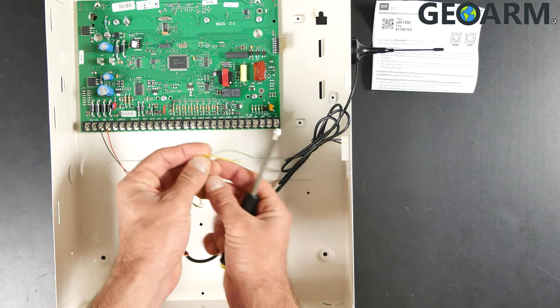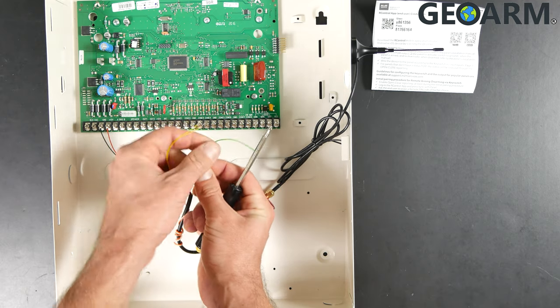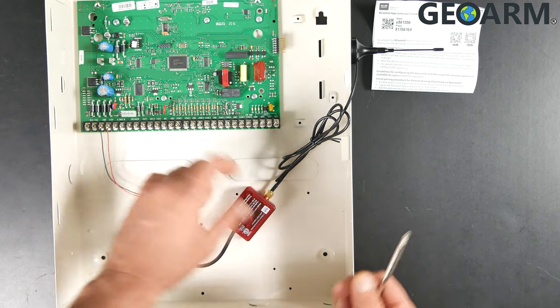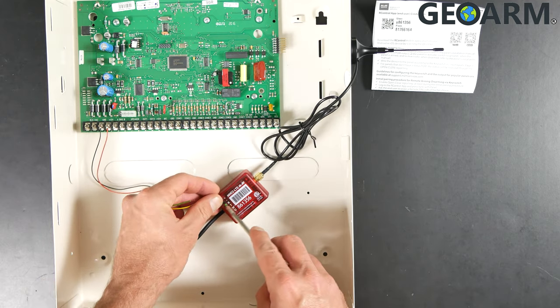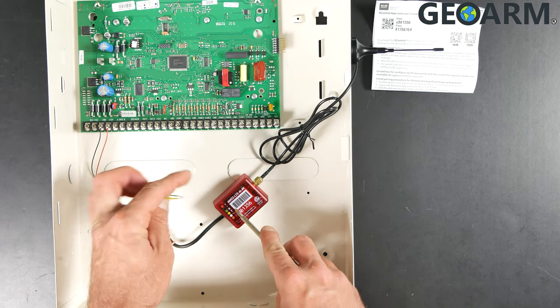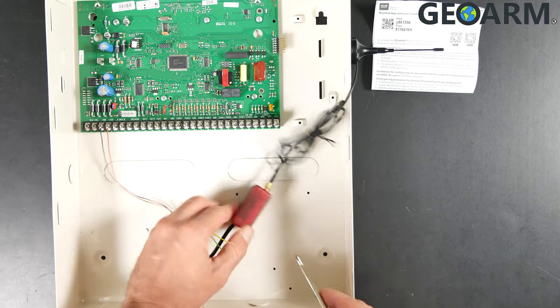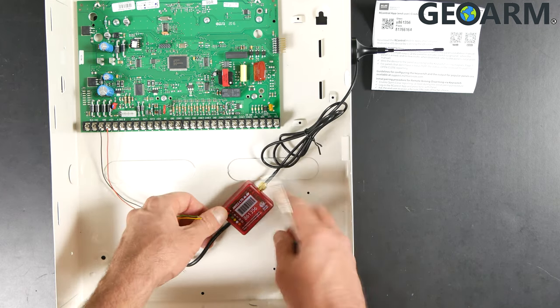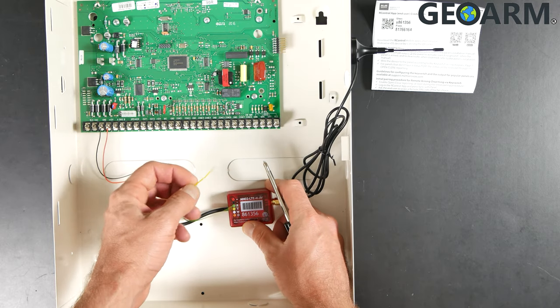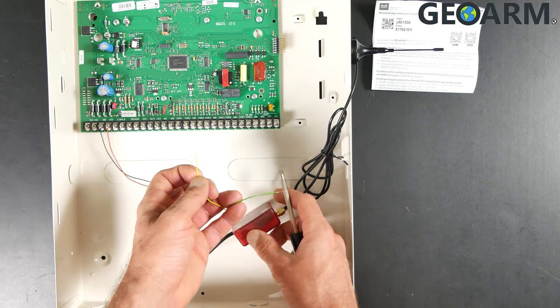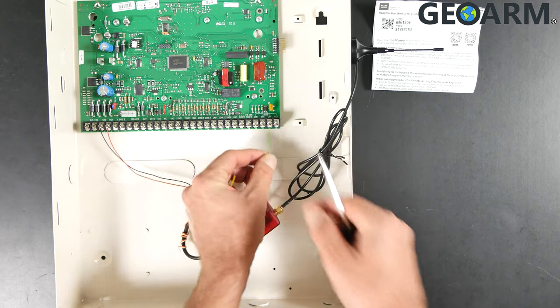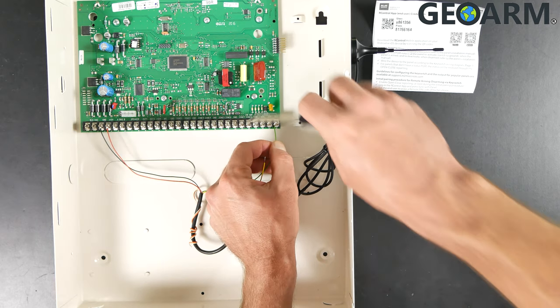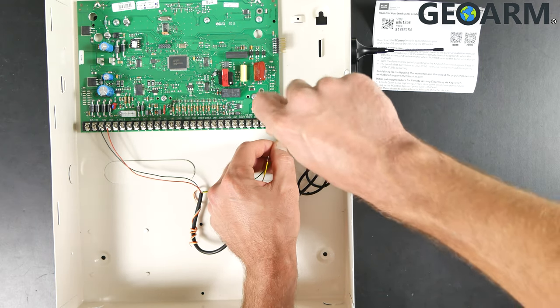Now, the next two connections we're going to make are the yellow and green wire, which are going to be for tip and ring respectively. As you can see, it's already labeled on there. So we're going to go with the green wire to terminal 28, which is ring. Get that tightened in place.